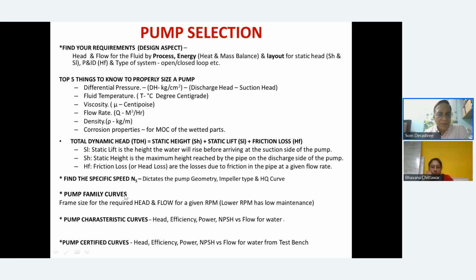Pump family curves, we have to find out. We get the frame sizes, required head and flow for a given RPM. Now, what is the RPM of the pump? Normally, it depends on the poles of the motor that you're using, directly coupled with the pump.